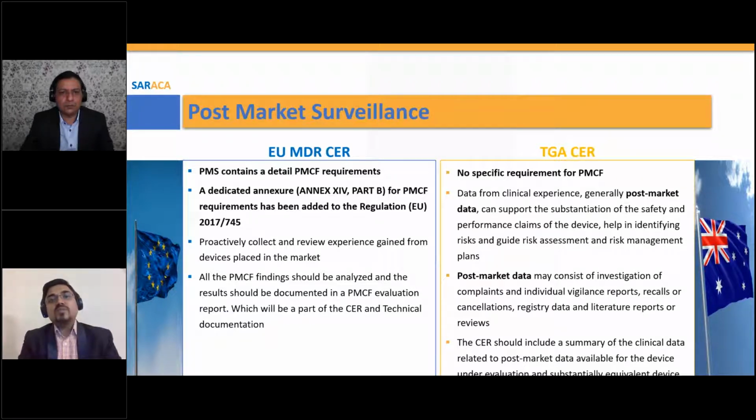So in most cases a PMCF is required, like for all high-risk devices or novel devices. You need to have a PMCF report in place to get approval for a clinical evaluation report. From the PMCF report, you can get all the main findings.